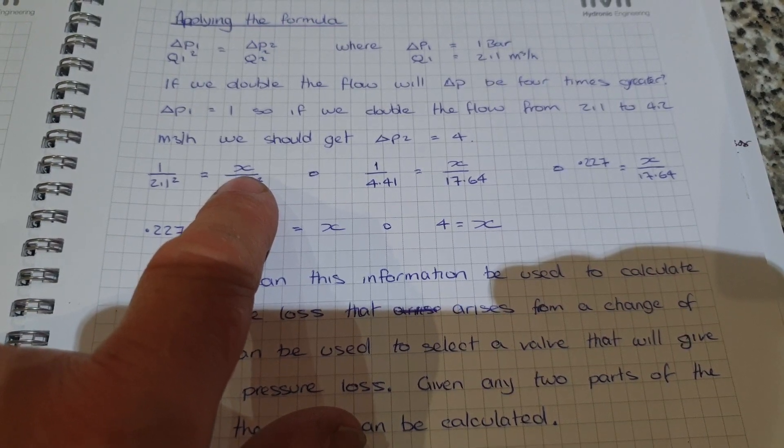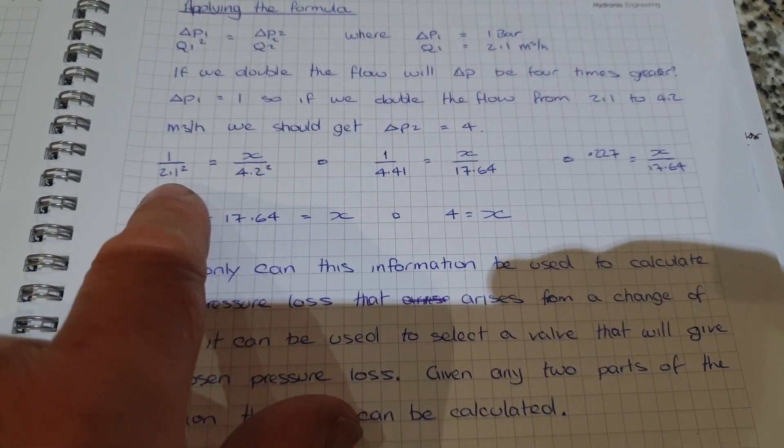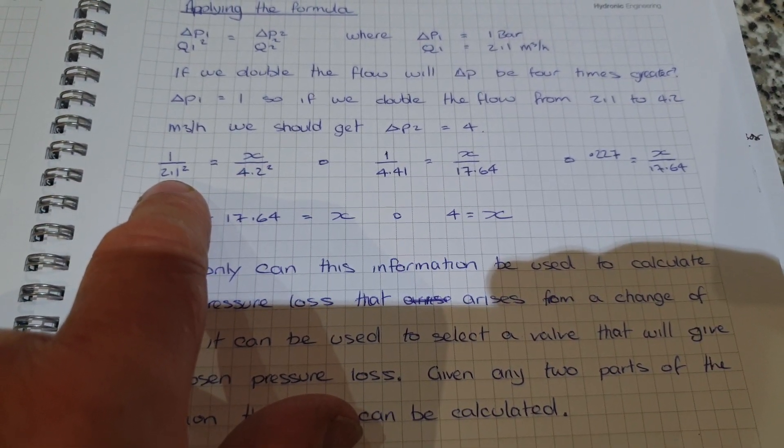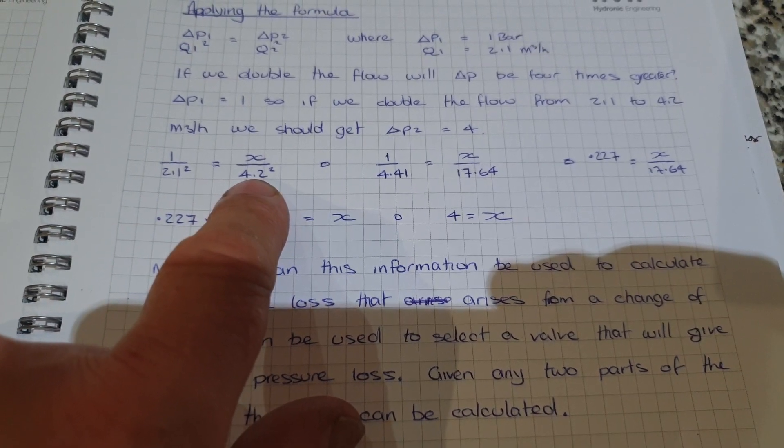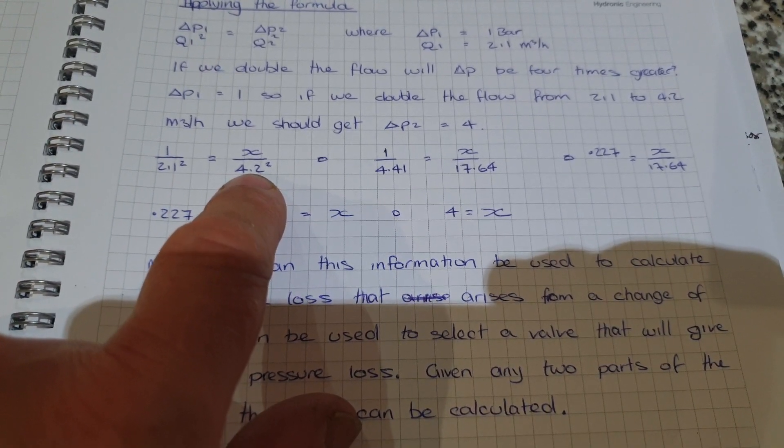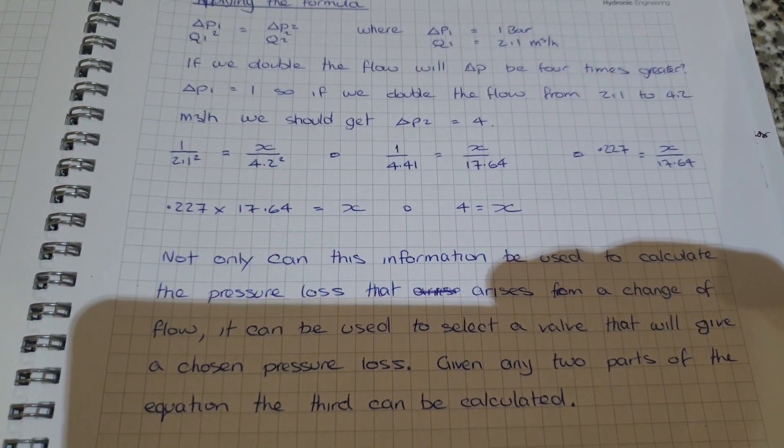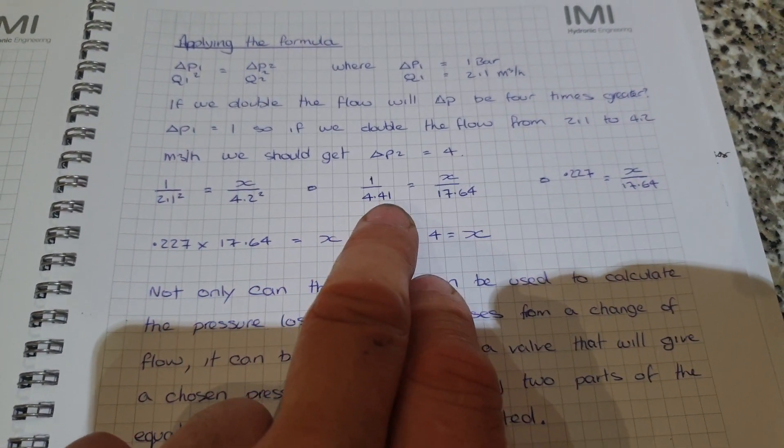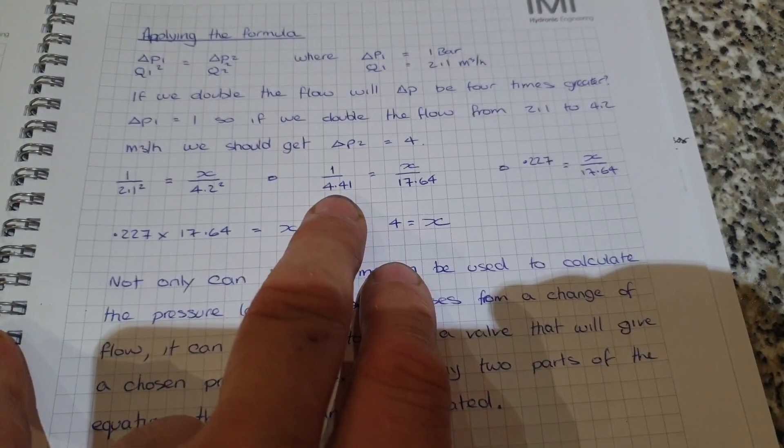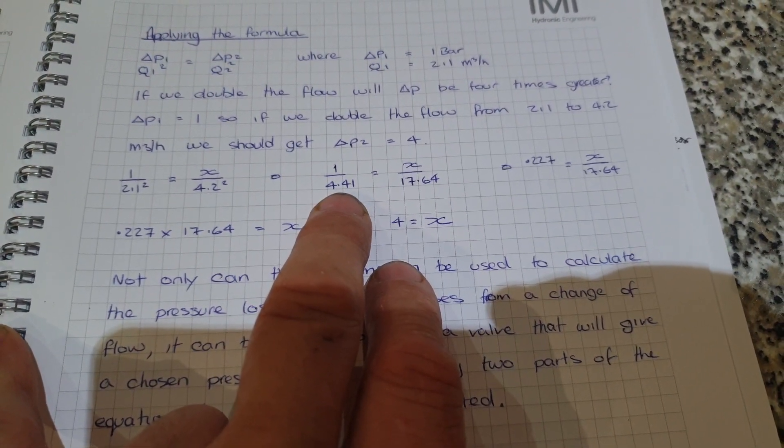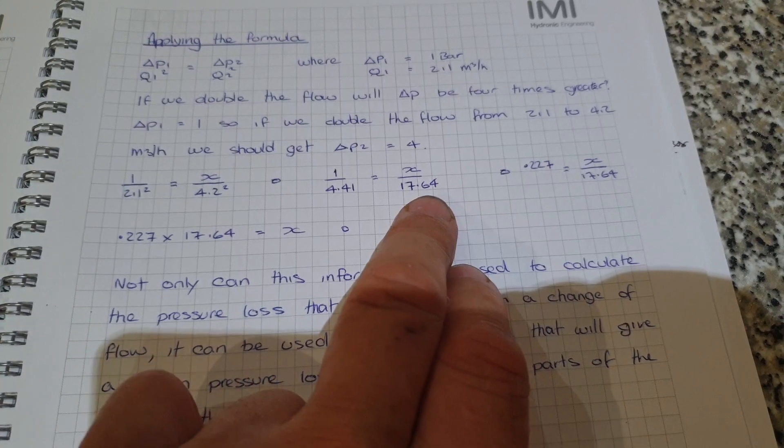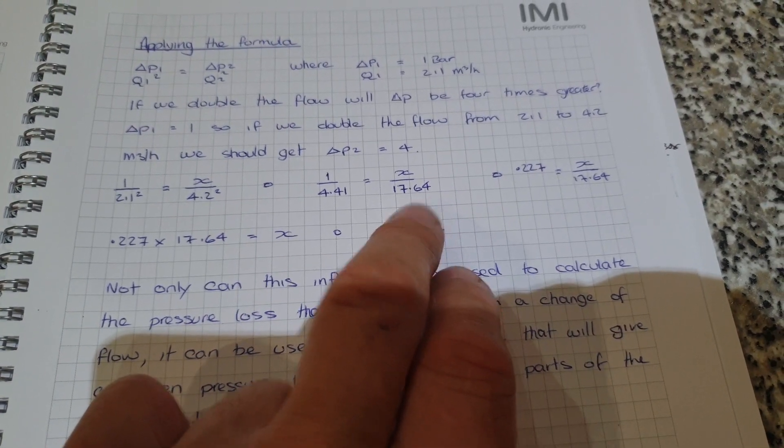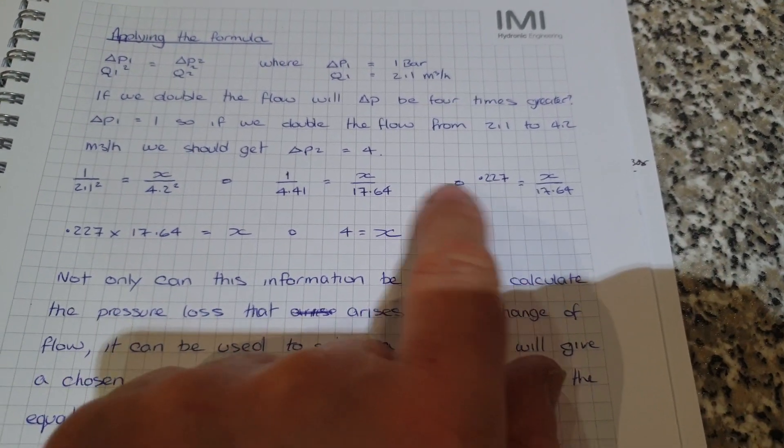We're trying to work out what our pressure drop will be if we double the flow. We've got 2.1 cubic meters per hour, we've doubled the flow to 4.2 cubic meters per hour, and we don't know what the resulting delta P will be. We'll break it down: we'll do the square of 2.1, which is 4.41, and we'll do the square of 4.2, which is 17.64.